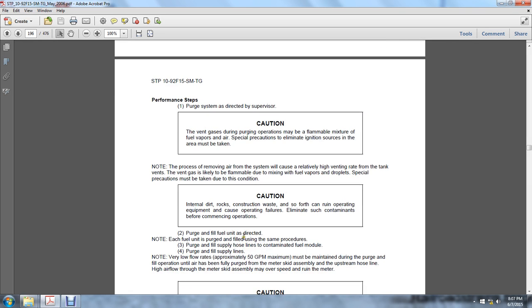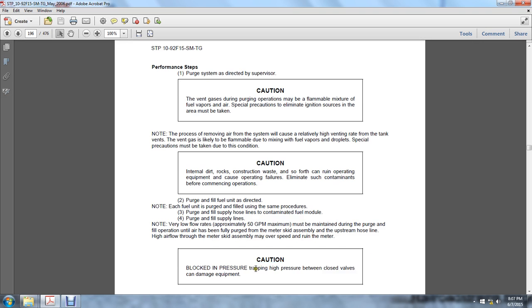2. Purge and fill the fuel unit as directed. Each fuel unit is purged and filled with the same procedure. Purge the fuel supply hoses, contaminated fuel module. Purge and fill supply lines. Very low flow rates, approximately 50 gallons per minute maximum, must be maintained during the purge and fill operation until the hose has been fully purged of air from the meter skids. Air flow in the upstream hose line from the meter skids may overspeed and ruin the meter.